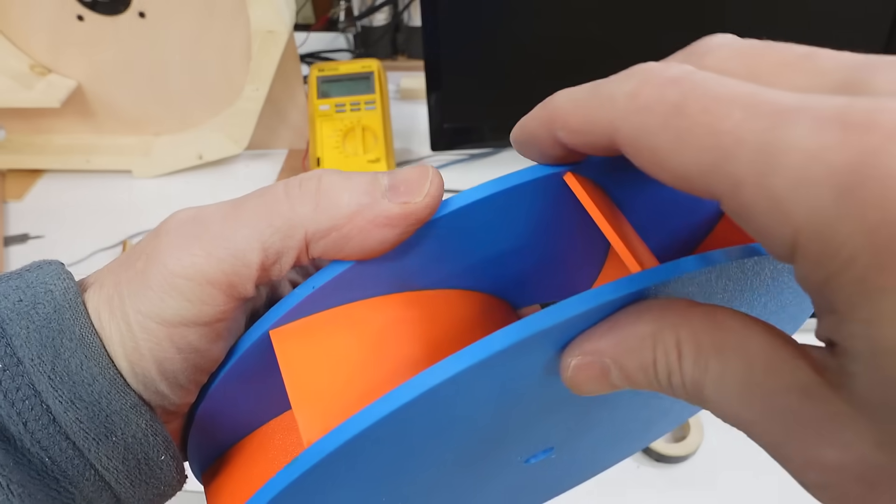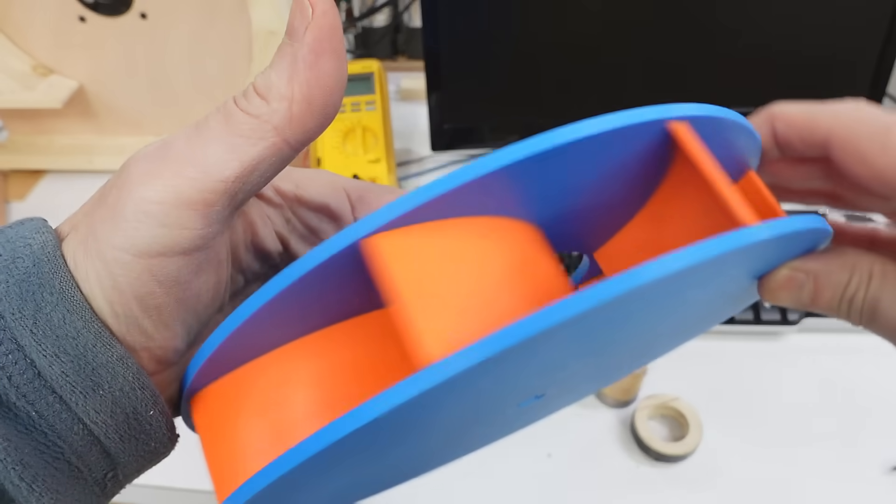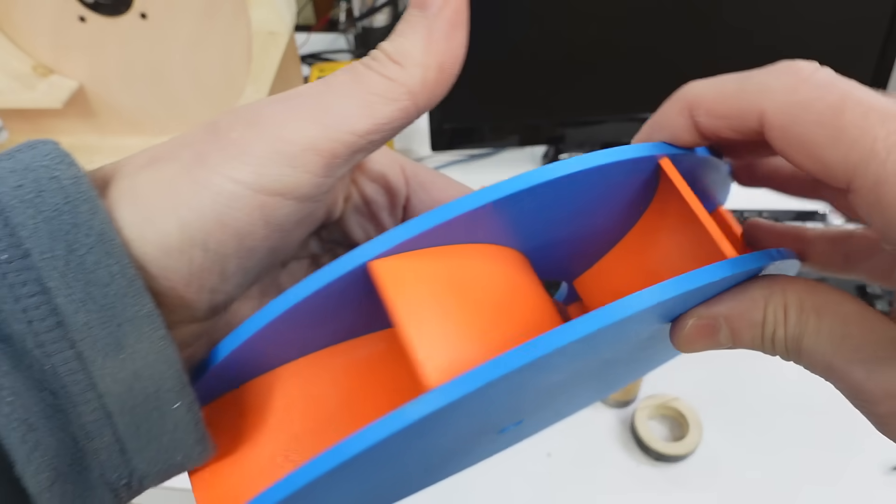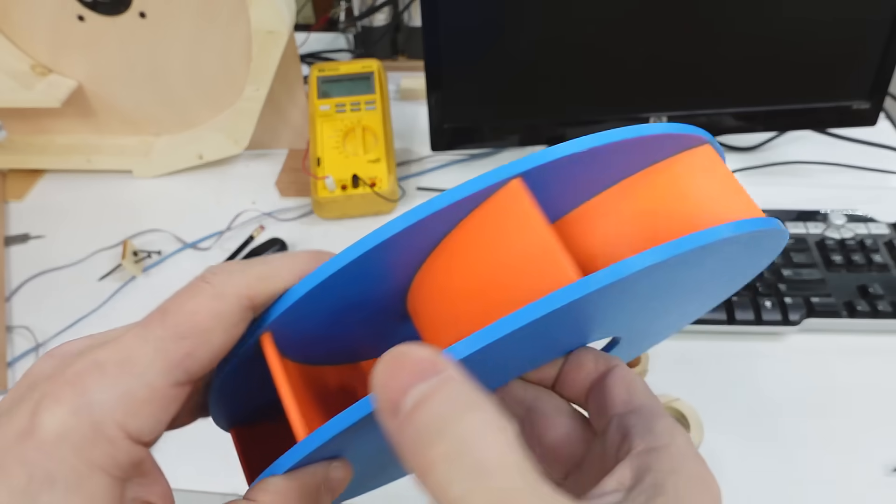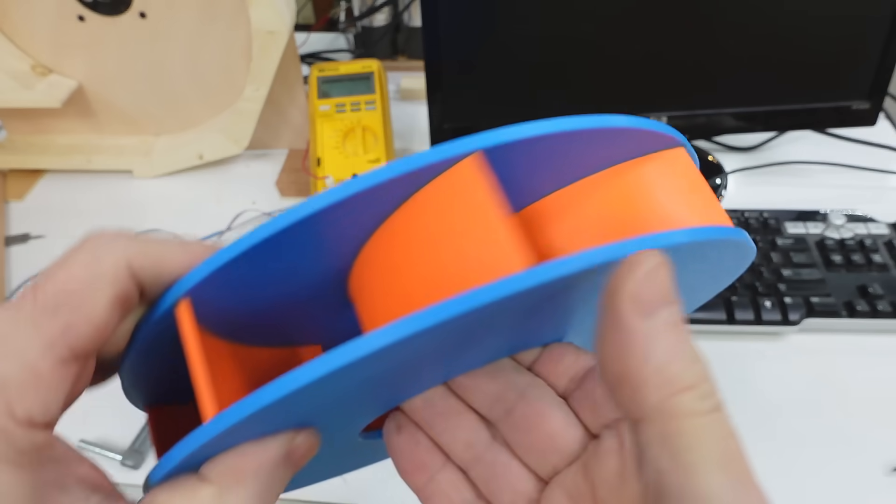I suspect the reason why the difference is bigger for the restricted air flow is that the impeller is just spending a lot of time just churning without that much air flowing through it, and the backward facing fins are just so much more aerodynamic in terms of sweeping past the air versus the front facing ones, which just causes a lot of turbulence. So for restricted air flows, the backward facing fins are definitely a win.